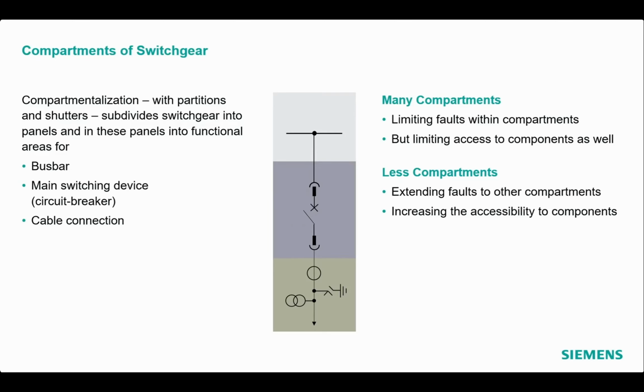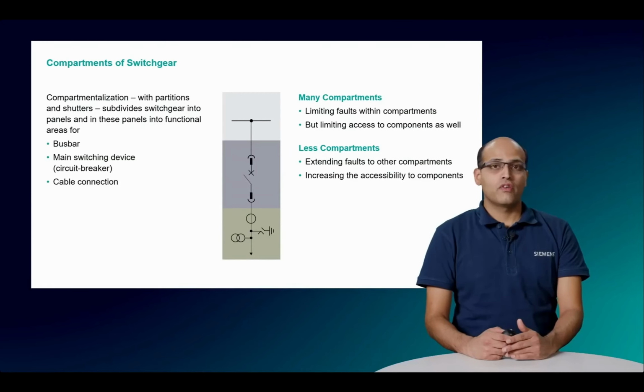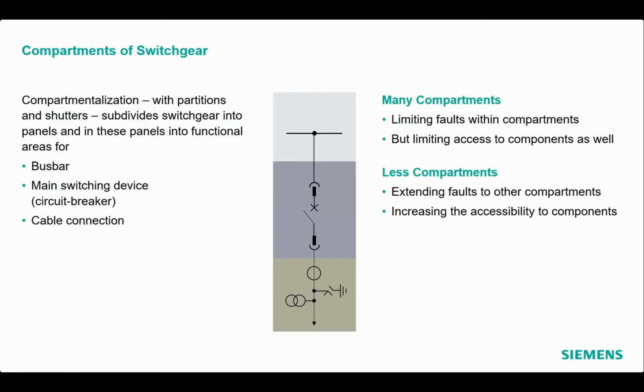Compartmentalization helps to enhance the reliability, safety, as well as the ease of maintenance. For example, a fault in one compartment can be contained without affecting other compartments. Similarly, repair works can happen in one compartment without shutting down the complete switchgear. Hence, in case there are many compartments, the faults can be limited within each compartment. At the same time, this would also mean that the access to the compartments is limited. On the other hand, if there are less compartments, the faults could extend, affecting other components as well. However, the accessibility to the components is increased.